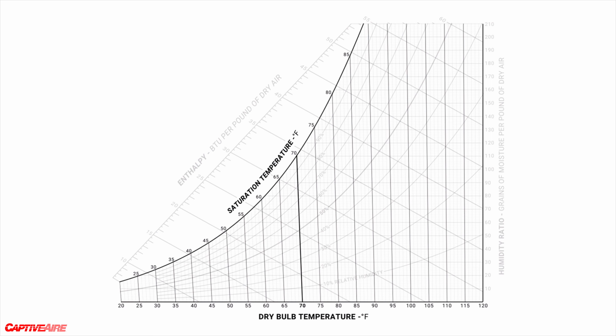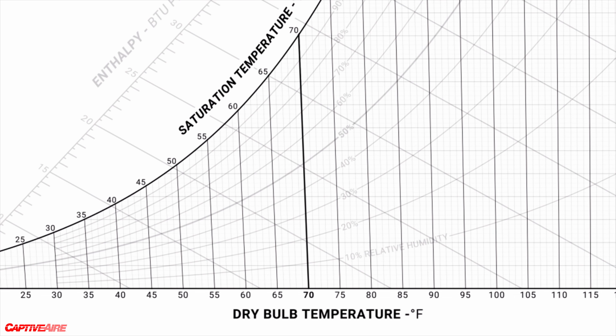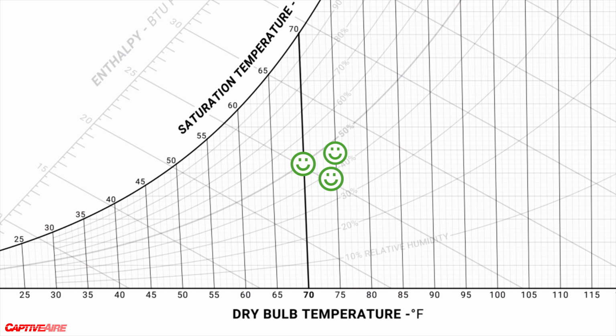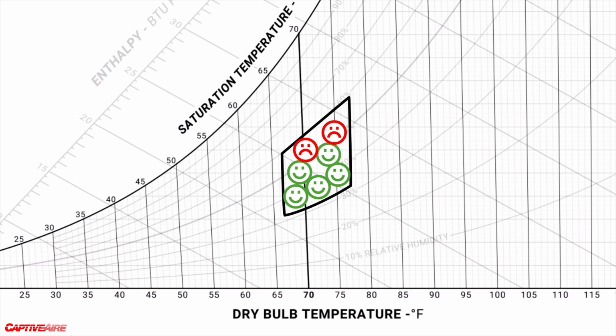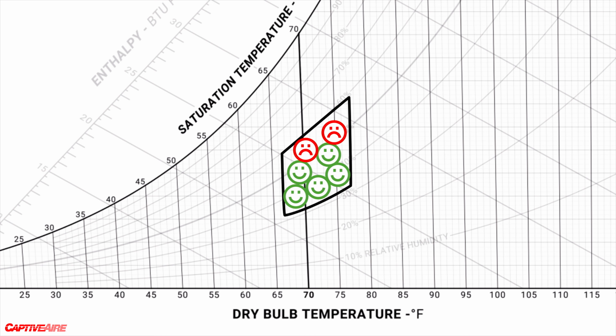And to be honest, we learned a lot from that, just on where set points are optimized. One example would be that every person seems to have a different perceived temperature or humidity level where they think, this is comfortable to me. ASHRAE gives you these windows of, all right, this is the comfort window if you're somewhere in here, but you still get one person to the next. One could be comfortable in the space, one could not be. So you want to get as many people in the group as happy as you can. What can we do to minimize the number of people who are uncomfortable through the space?